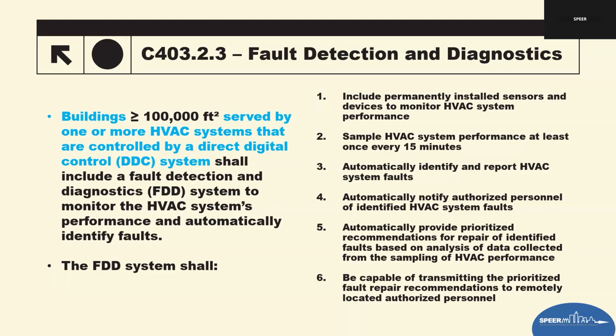What the FDD system must do is use permanently installed sensors to track HVAC system performance. It must sample performance continuously, every 15 minutes, with automated data collection; automatically identify and report faults when performance drops; notify authorized personnel when an issue is detected; provide prioritized recommendations for repairing the identified faults; and then transmit these recommendations remotely, not just locally.